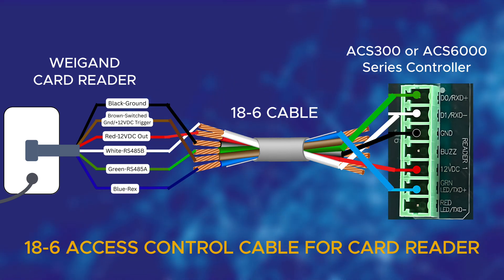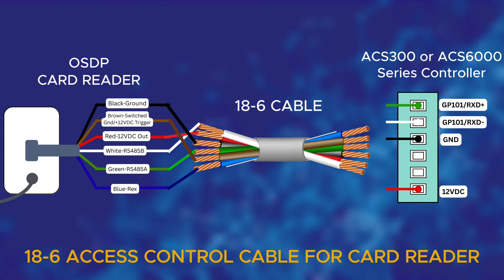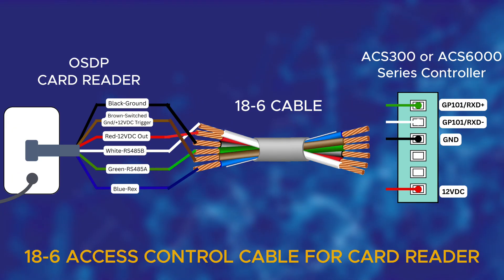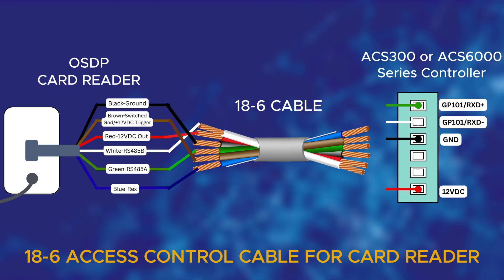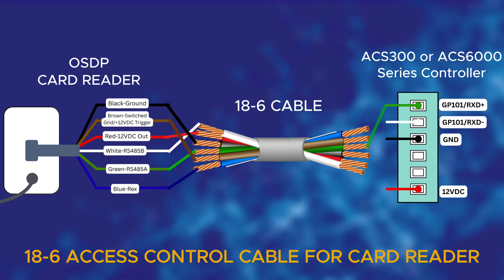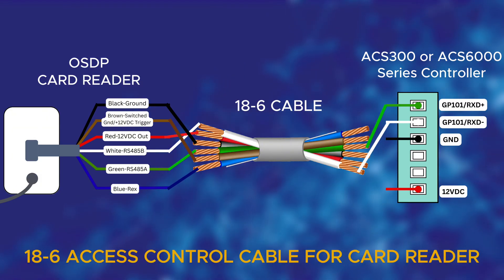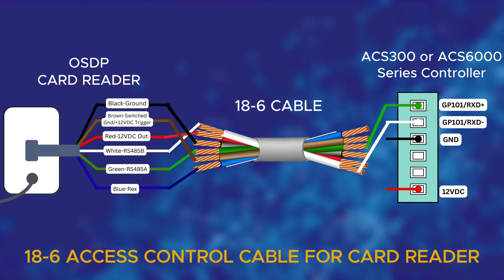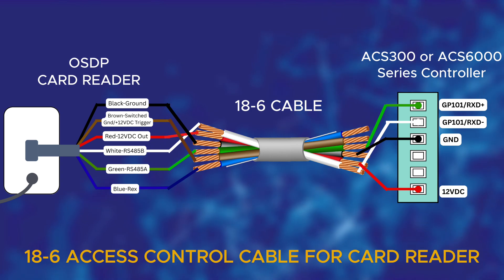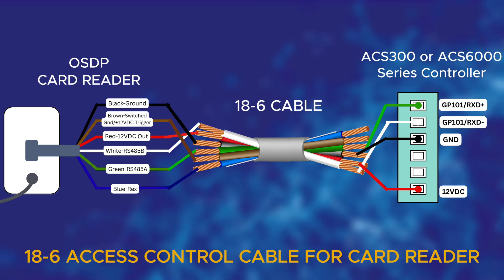Now let me show you how to wire the OSDP card reader to the ACS300 or ACS6000 series controller. The OSDP card reader wiring remains the same, but when connecting it to the controller, we'll only be using four wires. The green wire connects to GP101RXD+. The white wire goes to GP101RXD-. The black wire is for ground GND, and the red wire connects to 12VDC power. Make sure all connections are secure and matched to the correct terminals on the controller.